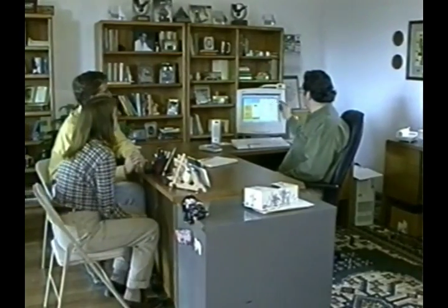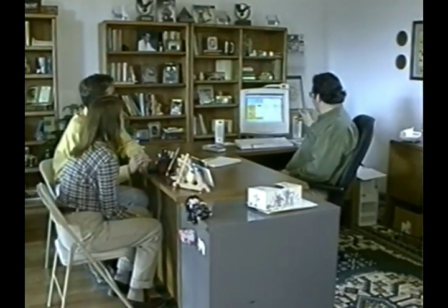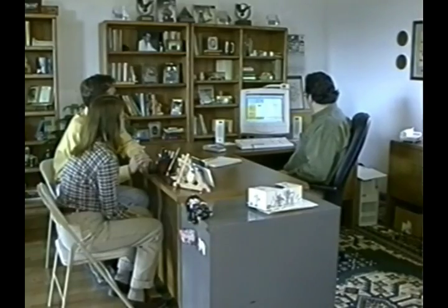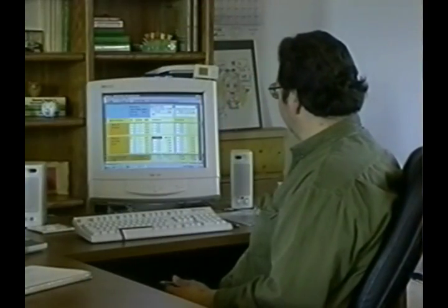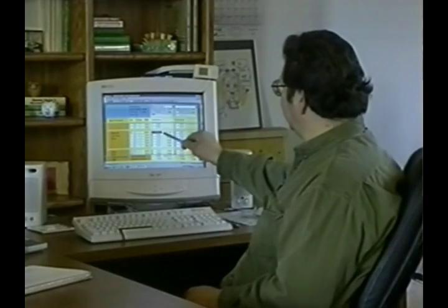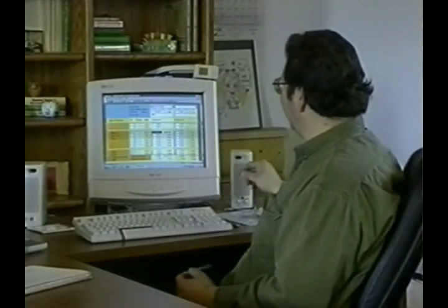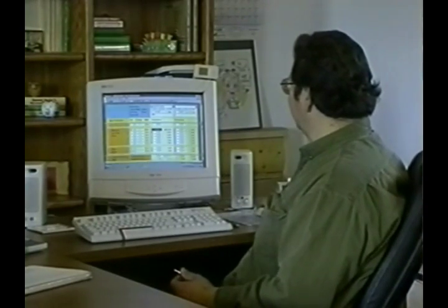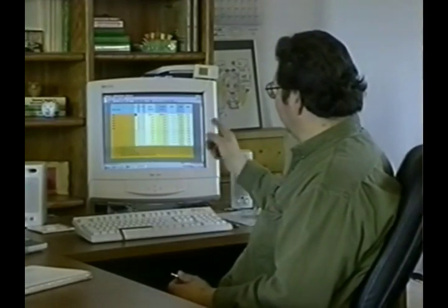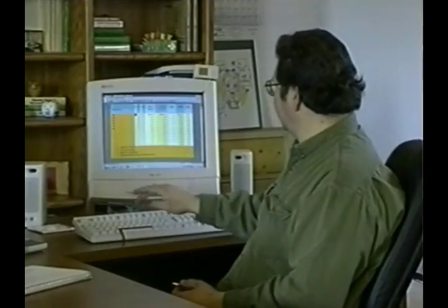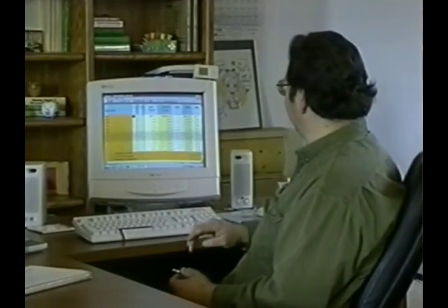Tube spacing and total tube length required varies according to BTUs needed to heat any given area. 1/2 inch diameter tubing at 9-inch spacing can provide more BTUs than 3/8 inch diameter tubing at 6-inch spacing. The tube size is calculated automatically on the MaxCalc program according to the specifications input into the program.